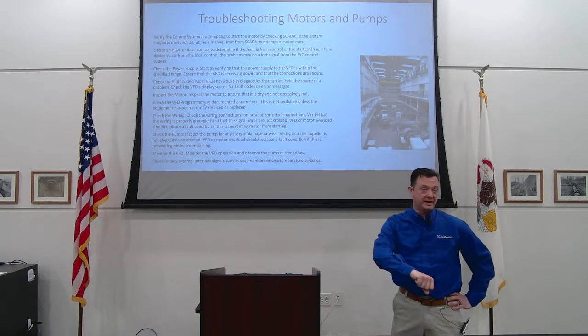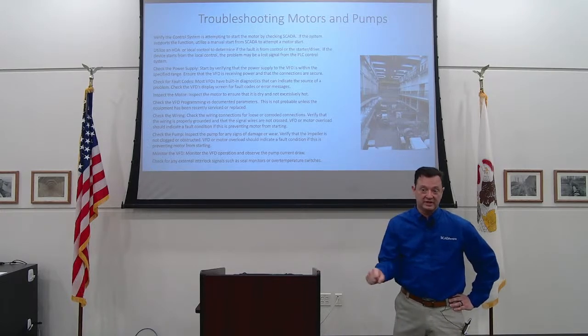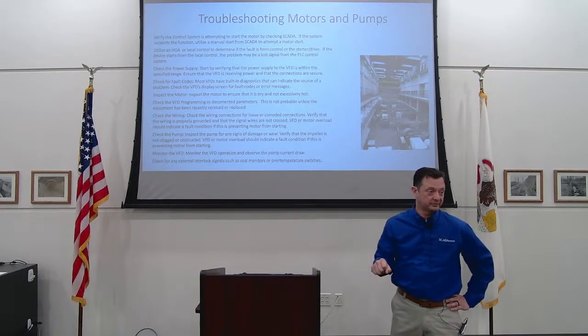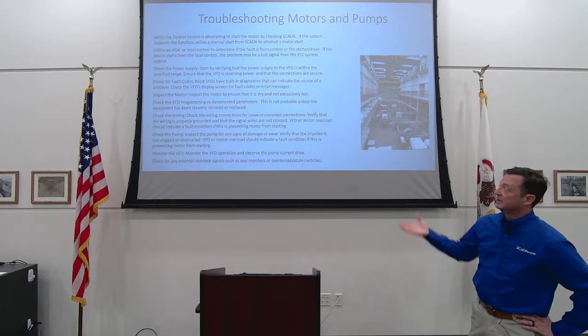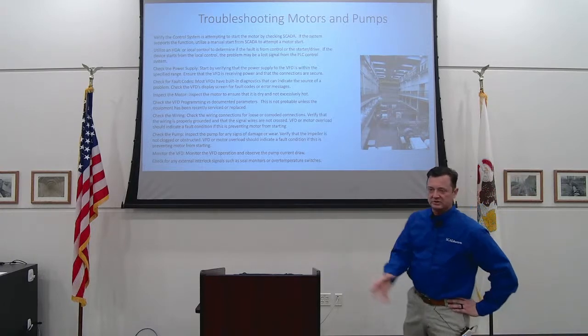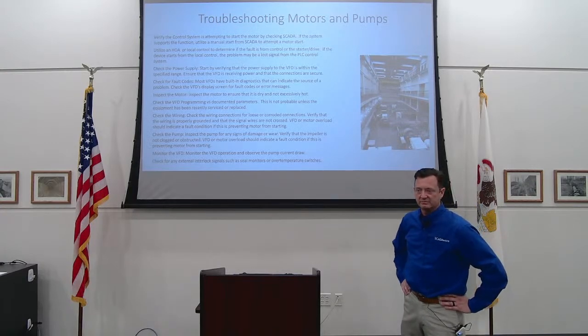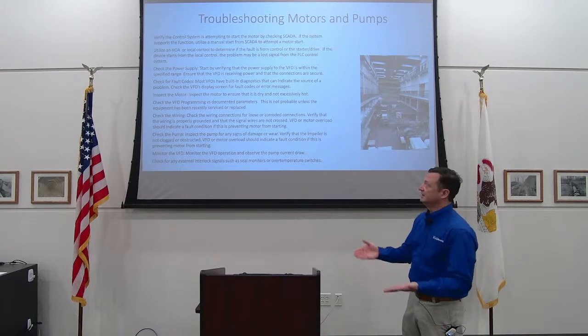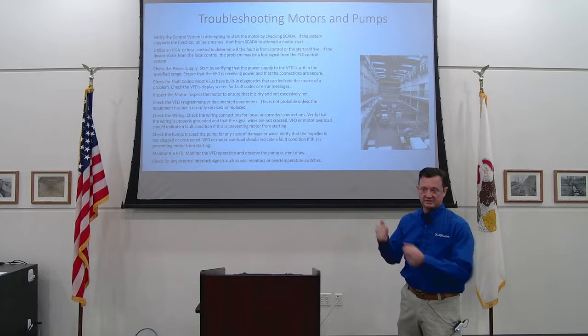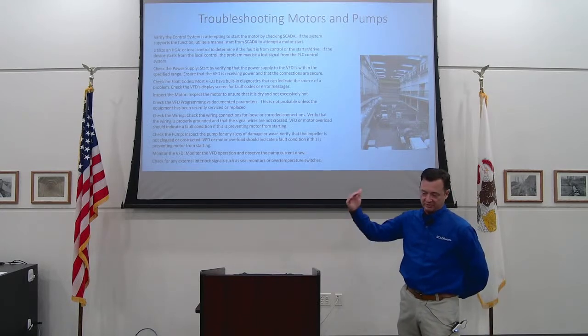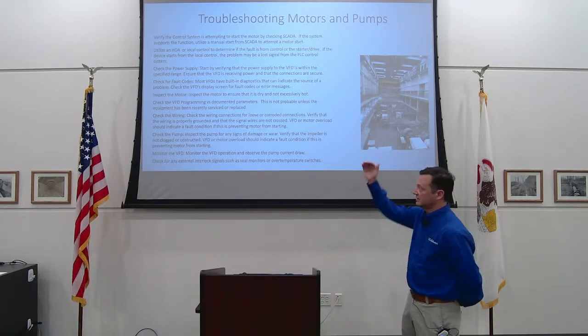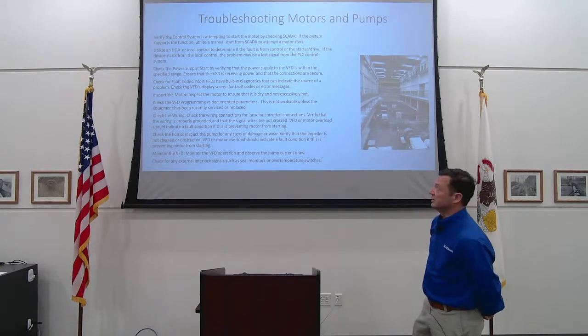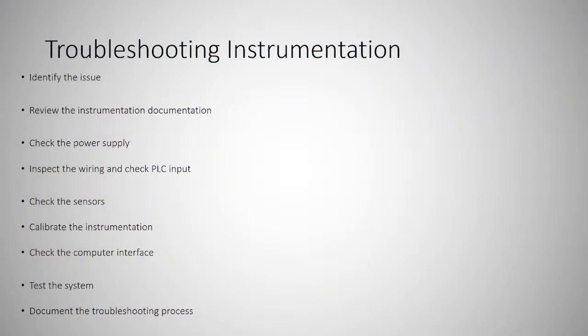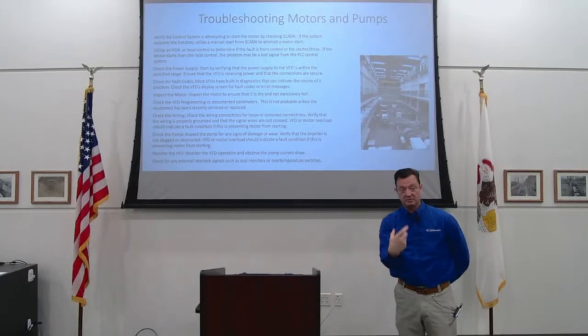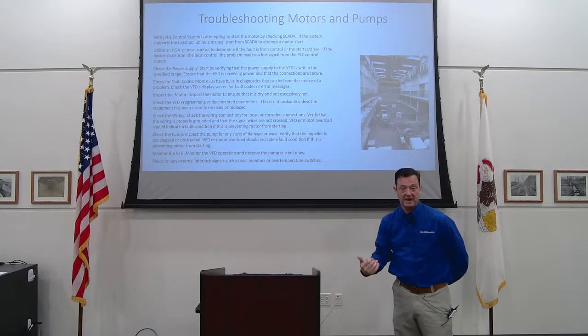If you put the pump in hand and it doesn't start locally, there's a really good chance it's going to be something electrical that an electrician's going to fix. But the next steps, and I don't know how much in the weeds you guys normally get as operators and from a maintenance perspective, the next step is to check power to the motor. I'm not sure how many guys are carrying meters with them, but this is the step where, if you've got a meter and you're comfortable with it, you can go through some of these other steps. And this is what the electrician is going to do as well. Check power to the VFD or the motor starter. If it's a VFD, go to the face of the VFD. If it won't start and it's got a fault, it'll normally tell you. It has a display on it, and that'll send you down the path that you need to follow.